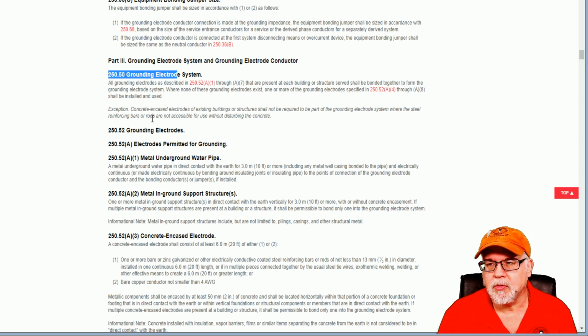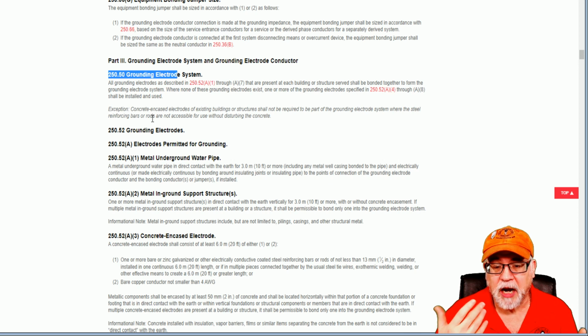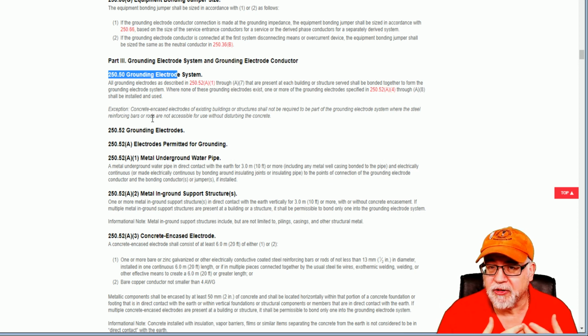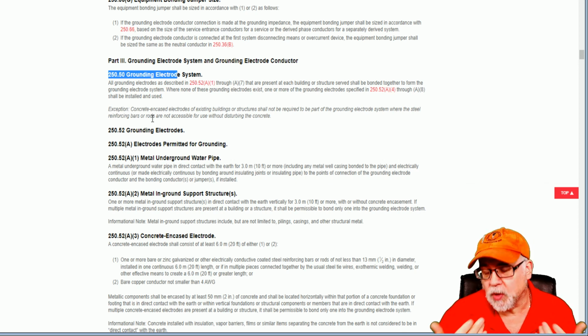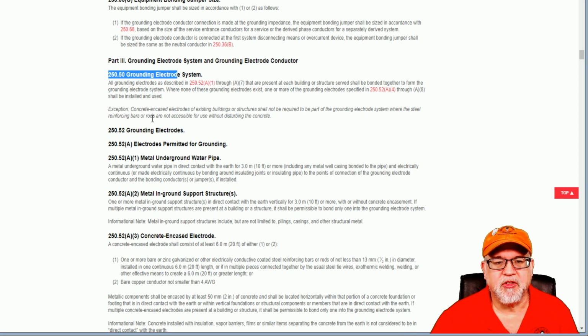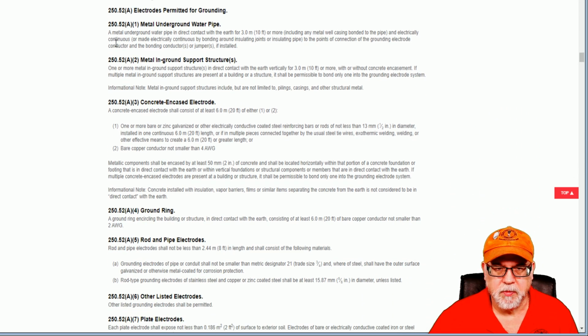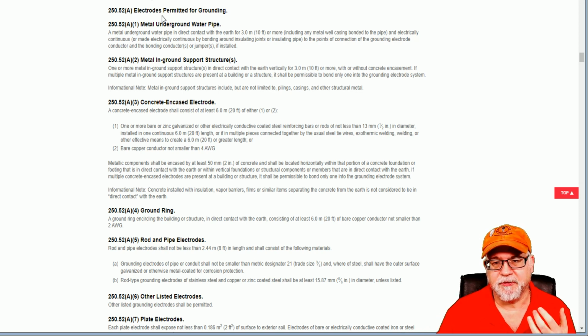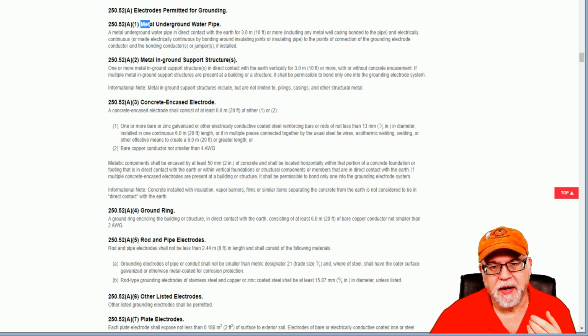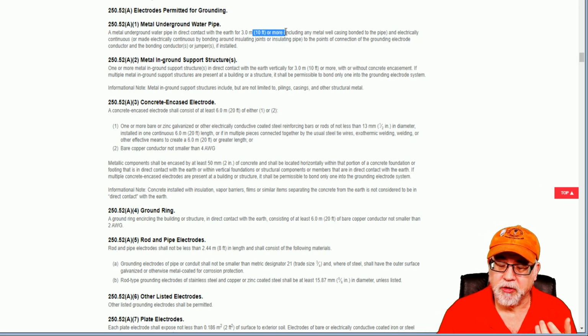So there are many engineers who have maybe a concrete encased electrode, which is 250.52(A)(3), and they might also require ground rods. Now, probably not necessary to have the ground rods because you don't have to supplement a concrete encased electrode. But if that's what the engineer wants, okay, they have to be tied together. So you have different ones. Then that takes us to 250.52, and this is where it starts to talk about the different electrodes. Of course, you see the water pipe right here, and if you see 10 feet or more in contact with the earth, then that would be an electrode. If it's there, you're required to use it.